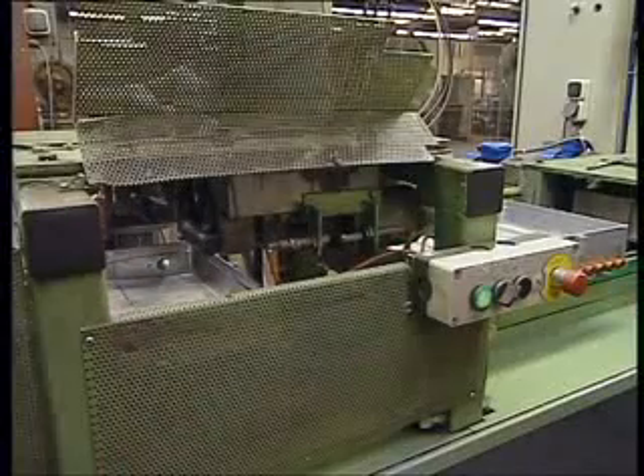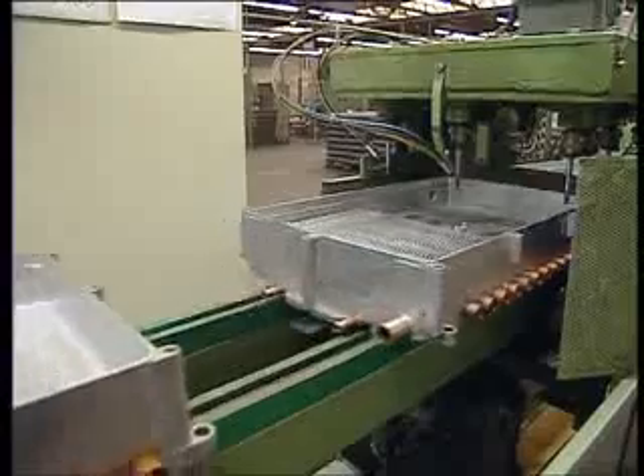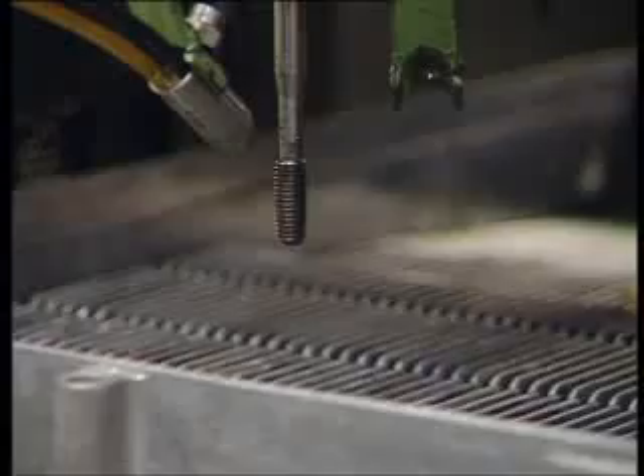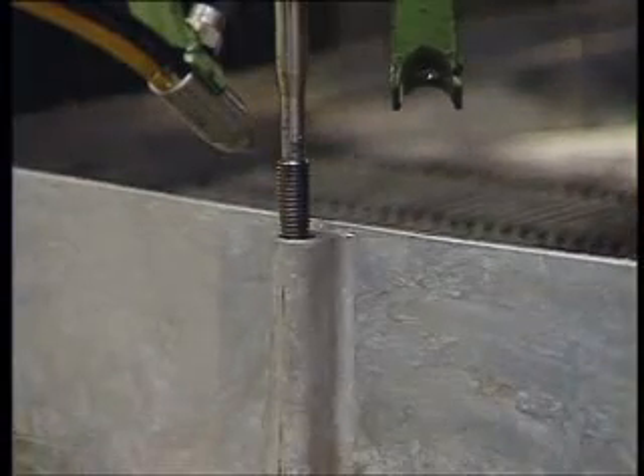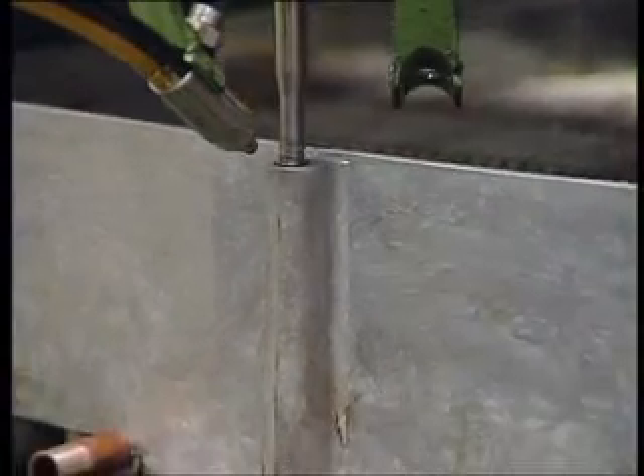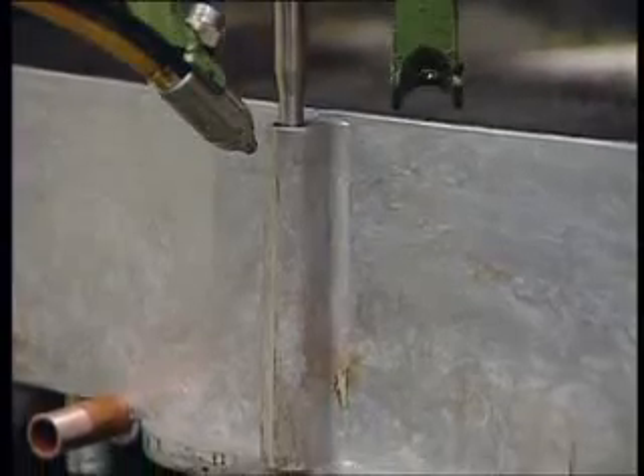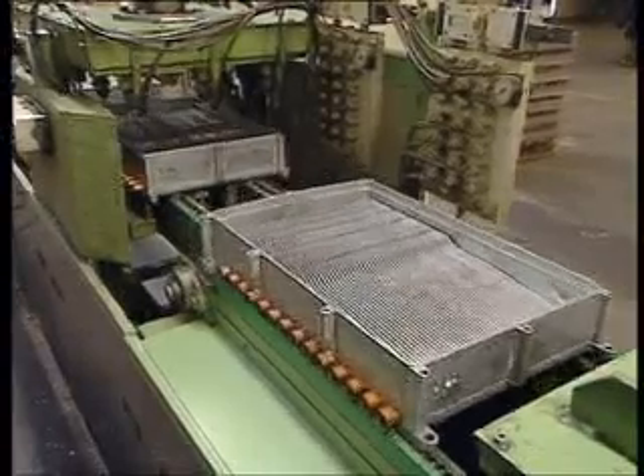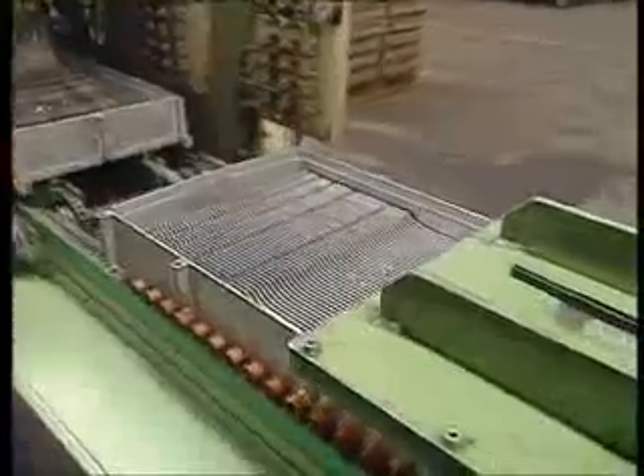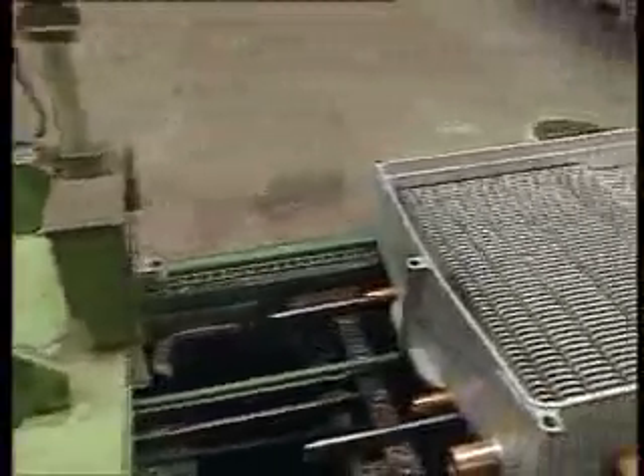In the beginning, the market reacted carefully, but when it was proven that the heat exchanger was reliable, the boiler was quickly prescribed in many building plans. It's a fact that the heat exchanger doesn't break down. Partly because of this, the Combi compact condensing boiler has become one of the most popular boilers in the Netherlands.